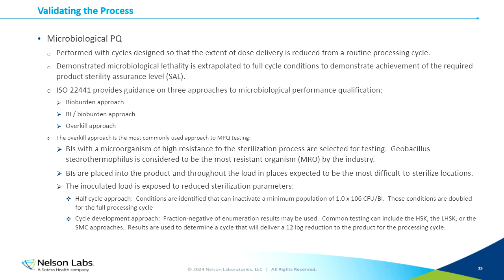The overkill approach is, first of all, performed with a microorganism, as mentioned, of a high resistance to the sterilization process. The microorganism you'll hear most commonly referred to as Geobacillus stearothermophilus, and this organism is what most in the industry consider to be the MRO, or most resistant organism. When purchasing BIs, this is the organism you'll most commonly come across. We take those BIs that we purchase or manufacture, however we obtain them, and we place those into the product and throughout the load in places that we expect to be the most difficult to sterilize locations.